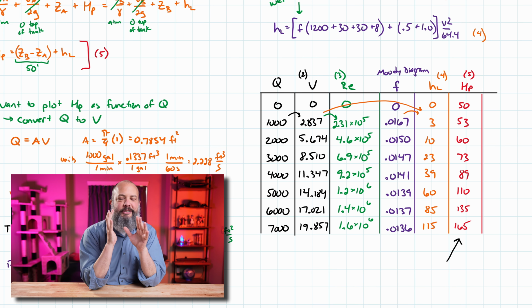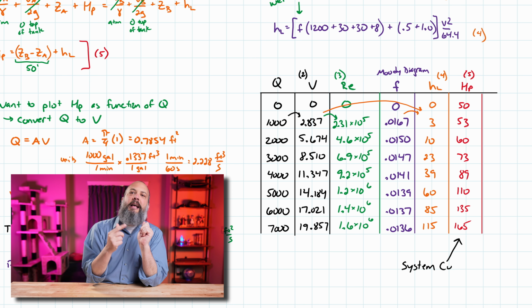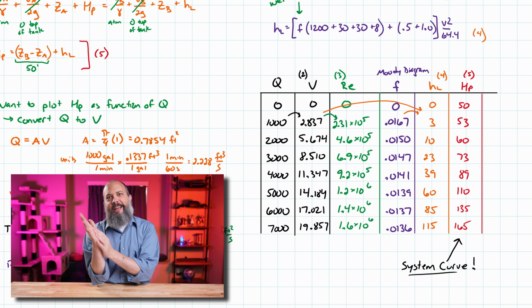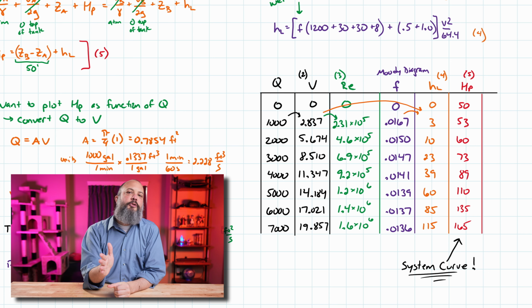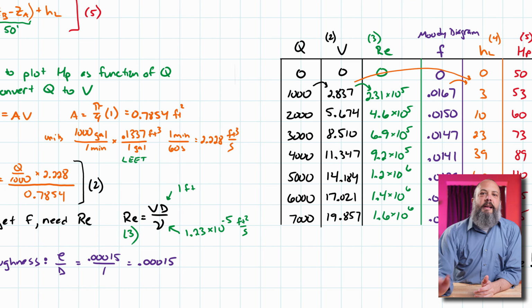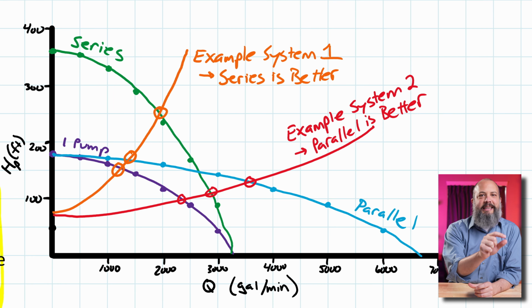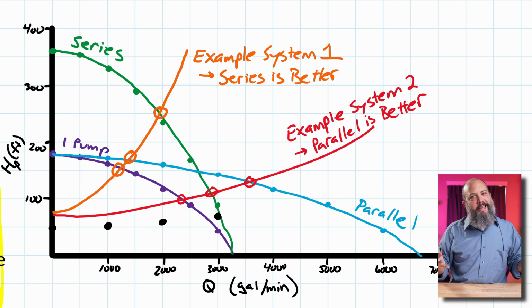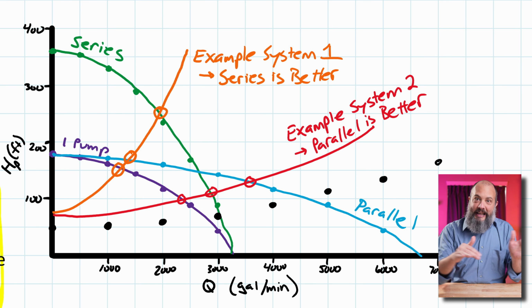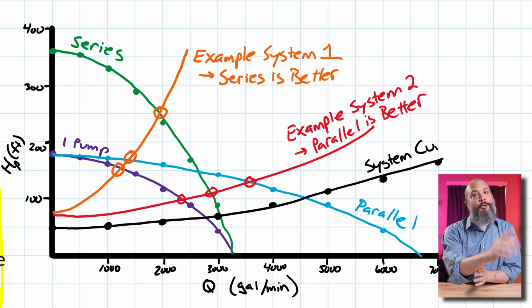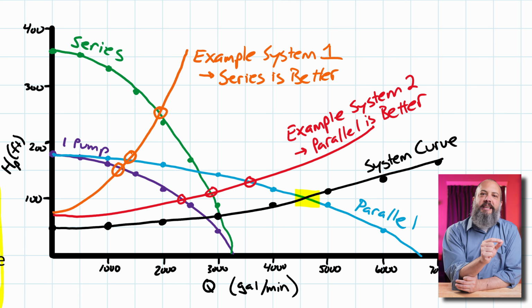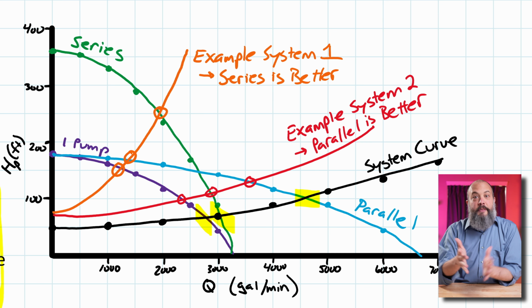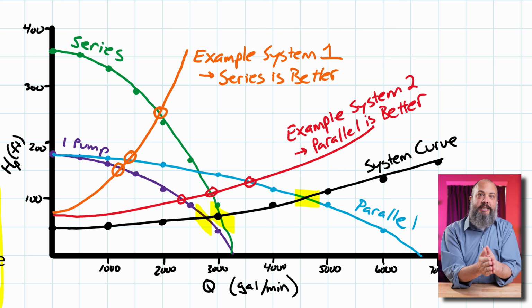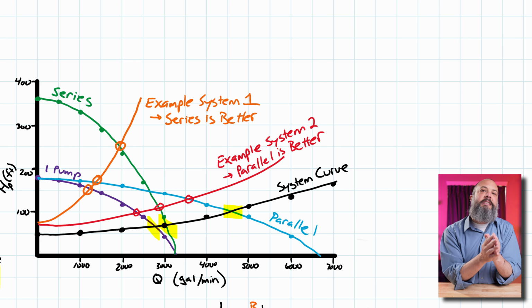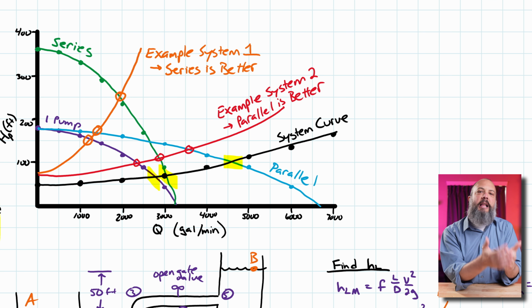And now we can go back to the original drawing where we have the pump curves and plot our new actual system, and finally see whether this particular system would do better with parallel or series pumps. I'm plotting each of these points as black dots on my system. You can see that this system curve is even lower, even flatter than my example system 2. Highlighting each of these operating points, where the pump curve crosses the system curve, that is going to be your actual operating conditions. That's the actual flow you will really get through the system and the actual pump head that is supplied by the pump.